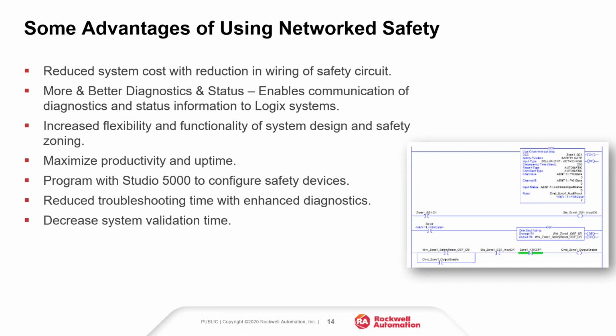One of its main benefits is reduced system cost and reduction in the wiring of the safety circuit. So in wired safety circuits, if you have a large machine and you wire it, then your safety system is what it is. It may interfere with production, but production will work around the safety of the system, and that may decrease production. So with Ethernet, with CIP Safety, we get better diagnostics and more information, more status. These devices, the drives, the VFDs, the motion drives, as well as light curtains, they all produce diagnostic data, and the data is useful in determining the reliability of the system.